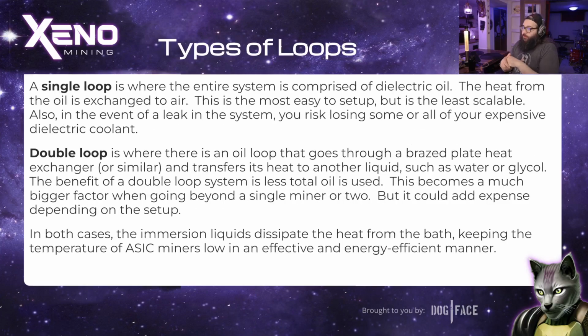Now, a single loop is where the entire system is comprised of dielectric oil. The heat from the oil is exchanged to air. This is the easiest to set up, but it's the least scalable. Also, in the event of a leak in the system, you risk losing some or all of your expensive dielectric coolant.